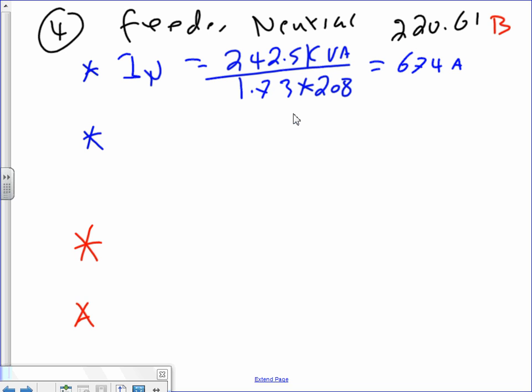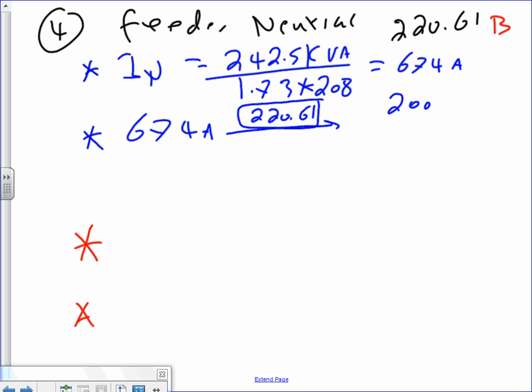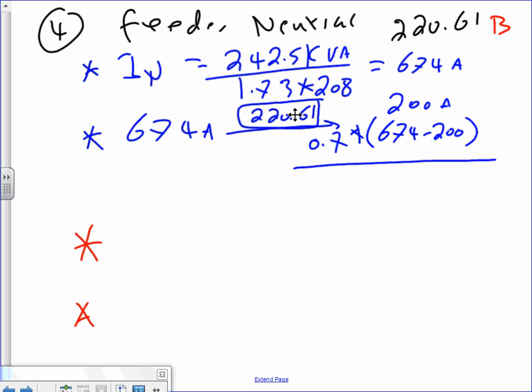Now the only step is you take 674 amps and apply the rating. You guys remember the 220.61 rule? You apply it. It says up to 200 amps, leave it alone. Higher than 200 amps, 674 minus 200, multiply by what? Anybody? 0.7. Add them up, and that will get you 532 amps. Remember that over 200 amps, we can derate them.